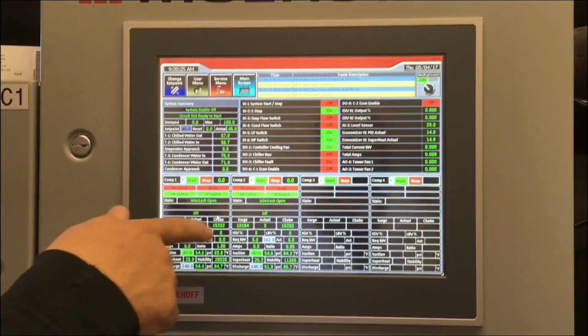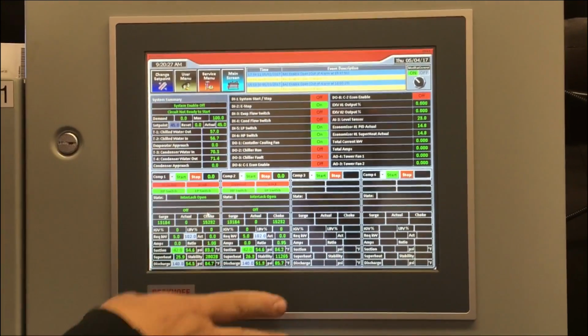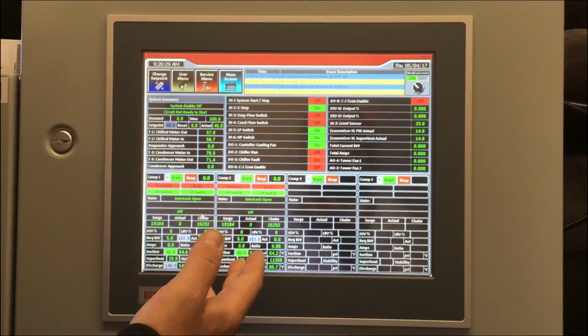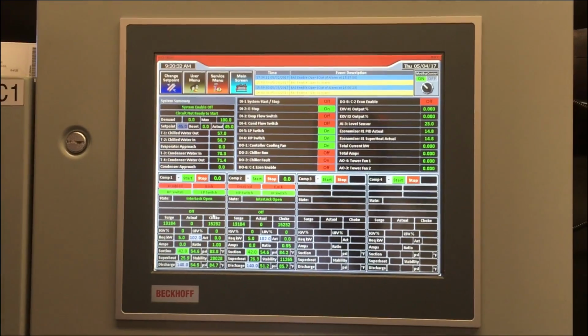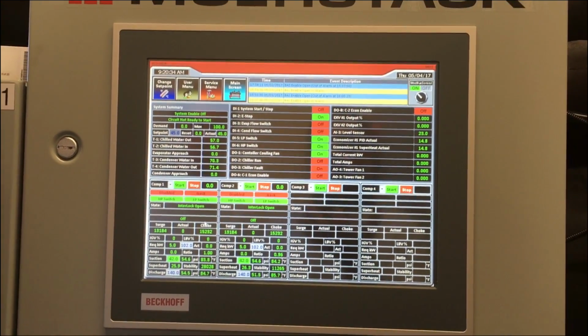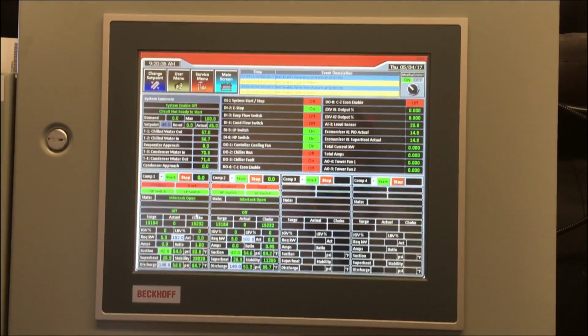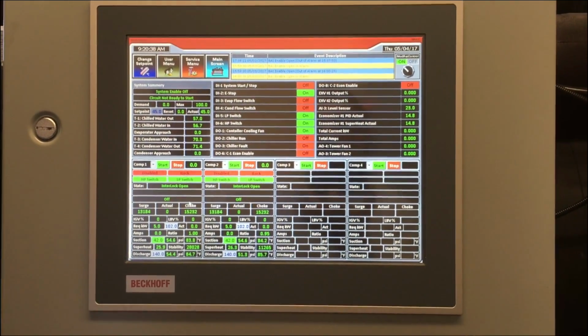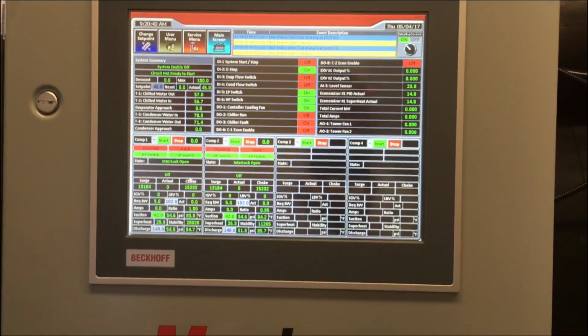I'm going to program that so that it doesn't look at it when the machine's not being called for. Because every time it's not being called for, right now you're going to go into fault. We don't want that. So in a 2-button push, I can have that only look at it when the machine's being called to run. And that'll get any nuisance alarms out of you.